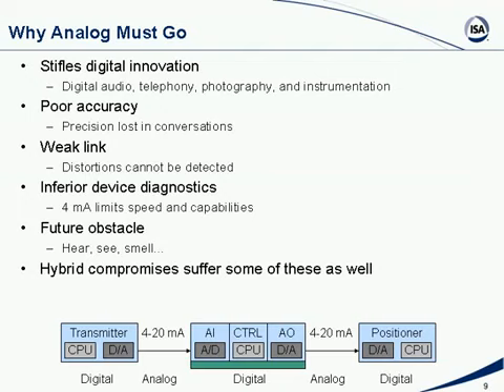Digital also gives better accuracy because you don't lose precision in digital-to-analog and analog-to-digital conversion associated with 4 to 20 milliamps, and you eliminate differences in current calibration between transmitter and receiver. Each conversion may only add a fraction of a percent of error, but it adds up throughout the control loop — from the transmitter to the controller input, the controller output, and then to the positioner, there are several conversions, and it all adds up.